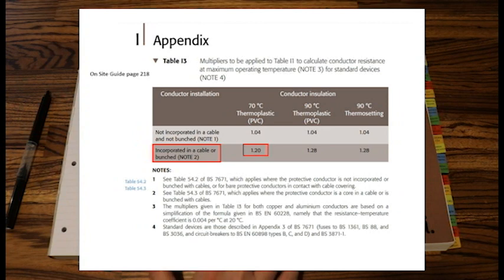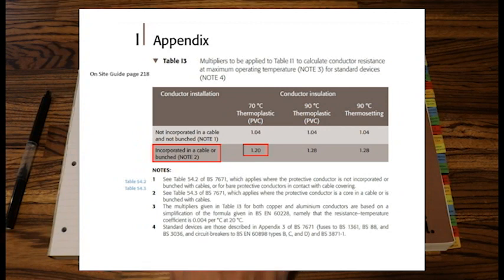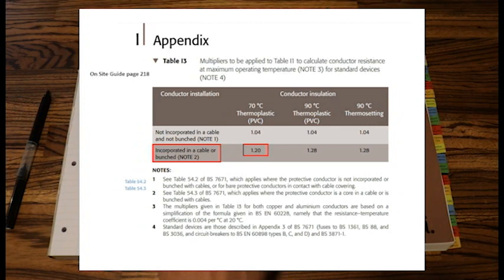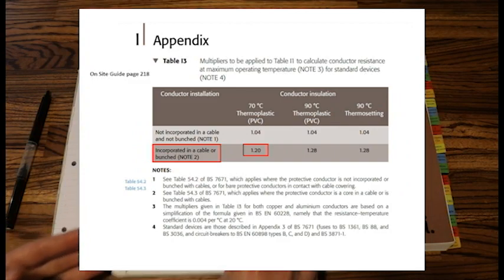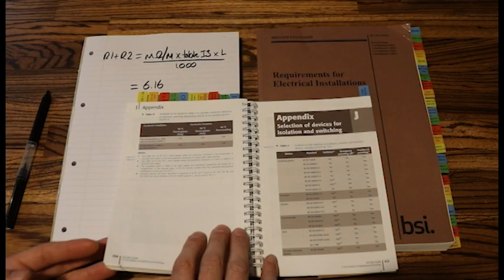So if you've got singles and no CG factor, it will be table I3, it will be value 1.04. For our question, we are using SWA cable. So it is incorporated within a cable. So our multiplier would be 1.2.